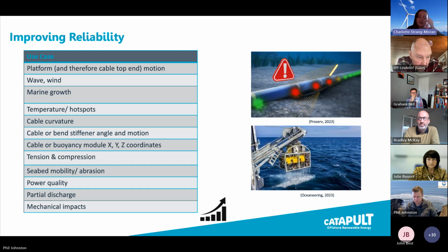Marine growth, we could look at external ROVs or AUV inspection, sub-CCTV cameras, infrared or depth sensors. If we want to understand the temperature hotspots through our cable, we can use DTS, which is distributed temperature sensing, which is a very well recognised and well-established technology used for fixed wind. We could also look at termination temperature sensing as well. If we want to understand cable curvature, we can look to internal fibre optic strain monitoring, which is your distributed strain monitoring. You could also potentially look to online line impedance resonance analysis, also known as LIRA.